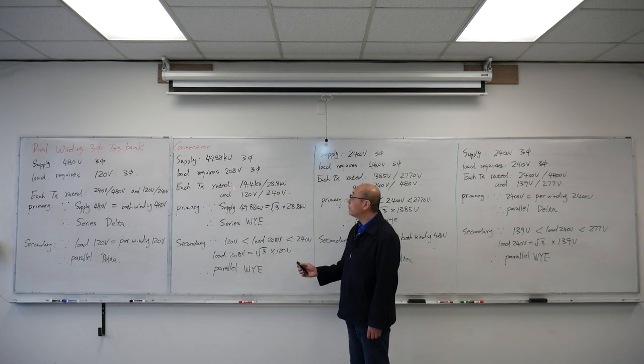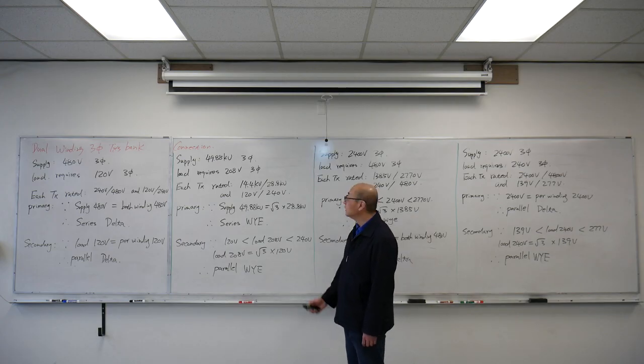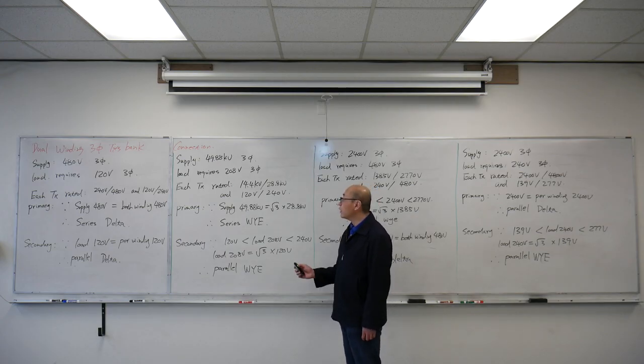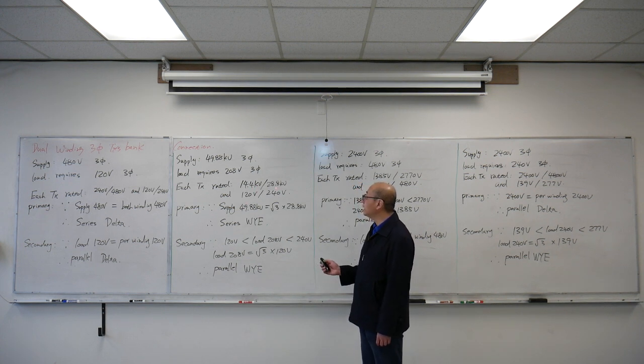Second example: my supply is 49.88 kilovolts. The load requires 208 volts. The transformer is 14.4 kV and 28.8 kV on the high voltage side, and 120, 240 on the low voltage side. This 49.88 kV is not equal to any of those numbers, so I know it's not going to be delta. Now I check if this voltage is higher than both of them. Yes, it's higher than 28.8. Then I check if 49.88 is equal to root 3 times 28.8. Yes, it is, so I know the primary side is going to connect in series Y.